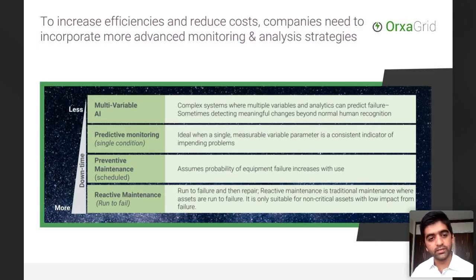Single node predictive monitoring would be like you are looking at a single parameter, such as on the transformer example, dissolved gases in the transformer oil. If dissolved gases go too high, that means there is a chance of breakdown. So beyond certain limits, you can basically do maintenance before problems materialize. Other things such as partial discharge and online monitoring tools usually provide these predictive maintenance strategies.